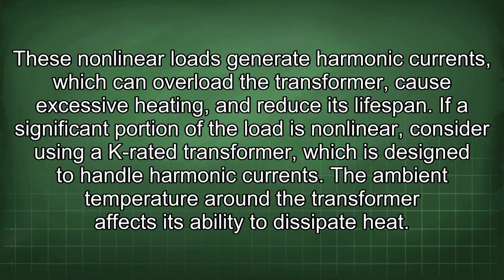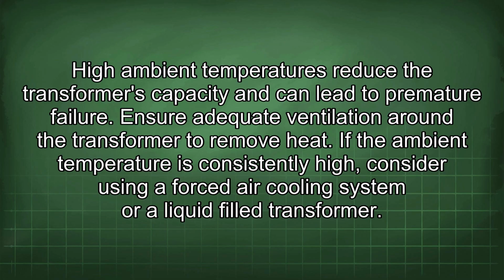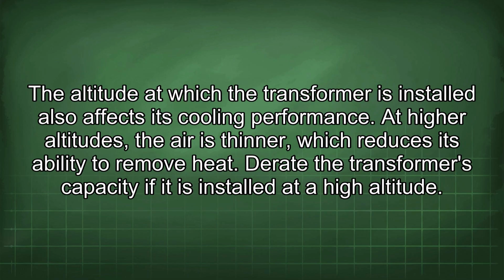The ambient temperature around the transformer affects its ability to dissipate heat. High ambient temperatures reduce the transformer's capacity and can lead to premature failure. Ensure adequate ventilation around the transformer to remove heat. If the ambient temperature is consistently high, consider using a forced air cooling system or a liquid-filled transformer. The altitude at which the transformer is installed also affects its cooling performance.